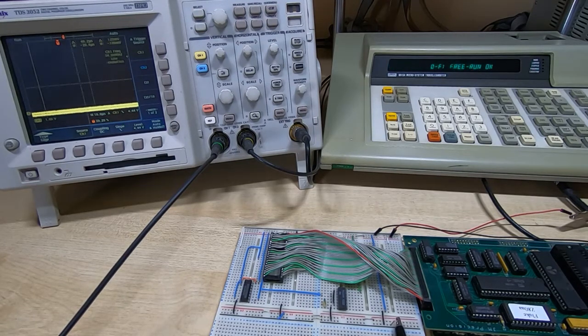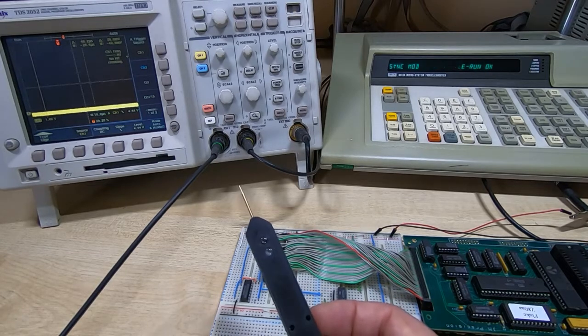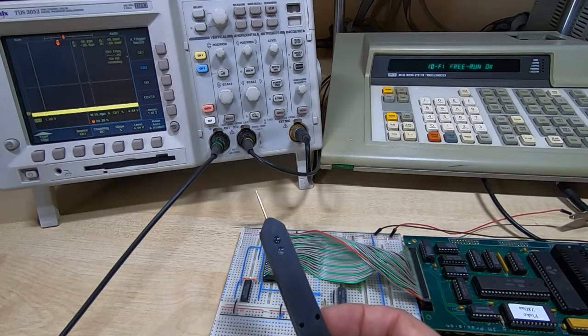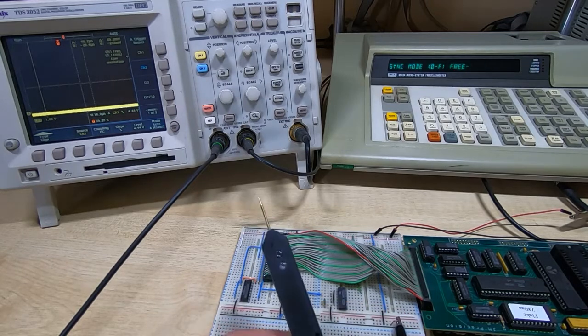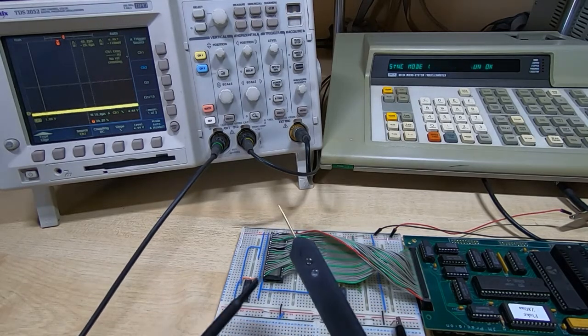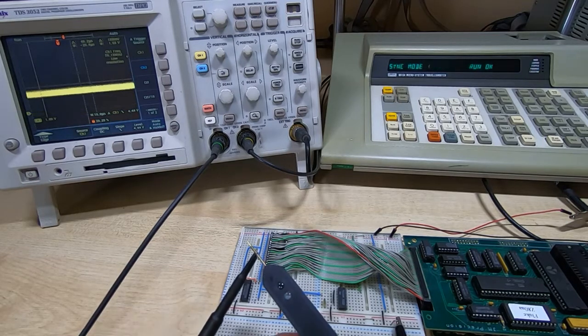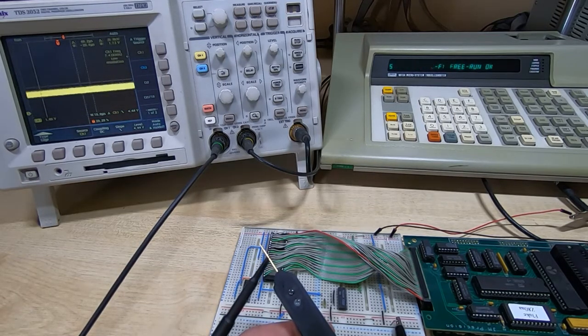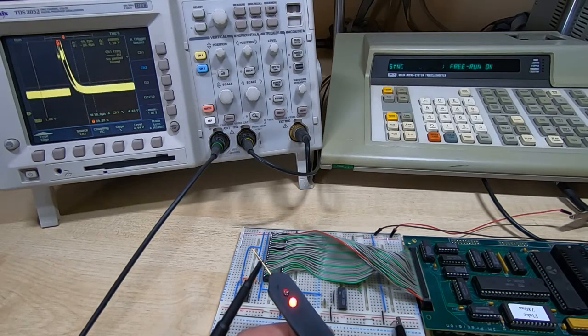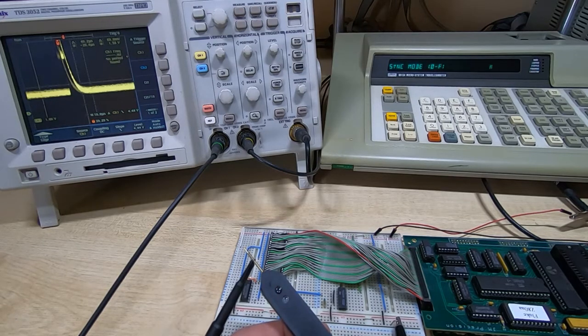So in general, the probe specification is quite straightforward. The default state is for the output to be floating. You can set it to pulse high or pulse low, so I'll attach the scope probe, and you can see that on the scope we are currently floating, so this is essentially tri-stated. We can then pulse high, so if I turn on pulse high, you can see we're now getting a series of high pulses coming out of the probe tip, and the red LED is flashing.